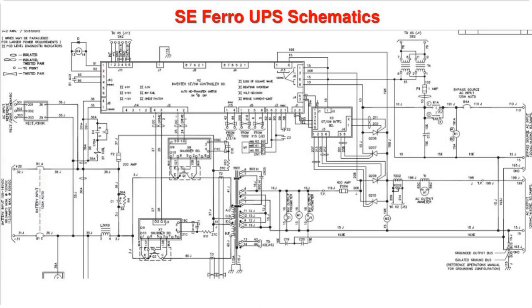We also have a monitoring circuit. So we're monitoring the DC here. We should have 135 volts there in normal operation. If that drops down to 105 volts, which is our low level voltage for the battery, the control board says, okay, I don't want to over discharge this battery any further because it could cause irreparable damage to the battery.